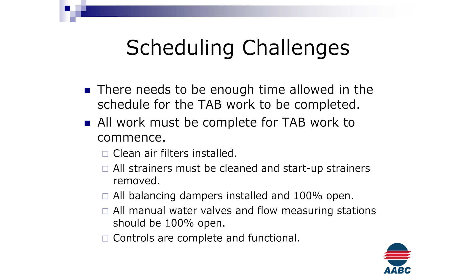All work must be complete for tab work to commence. Believe it or not, we need filters. We have to have them. We've got to have strainers. I've got to have a balancing damper or I can't do my job. Manual water valves and flow measuring stations need to be 100% open. I know from practice that mechanical contractors come in, install everything, and the first thing they do is shut a valve, right? They start shutting valves, and those valves may never be opened again until we get there.